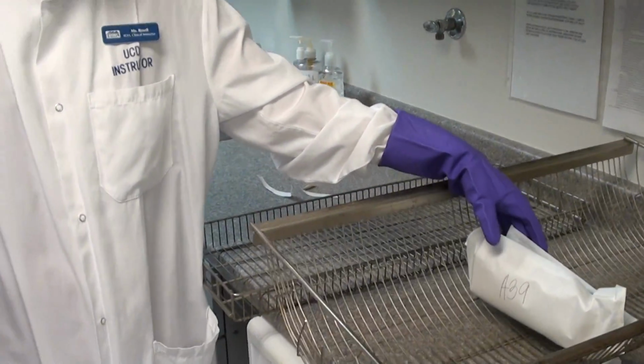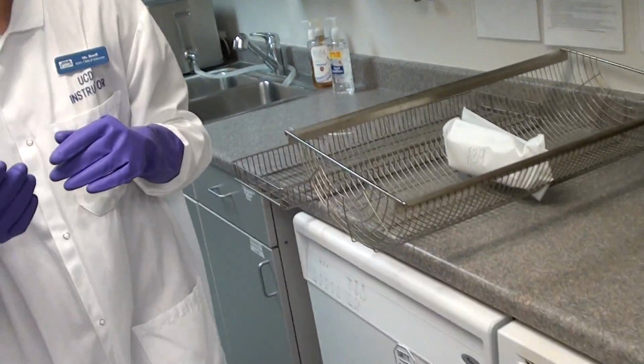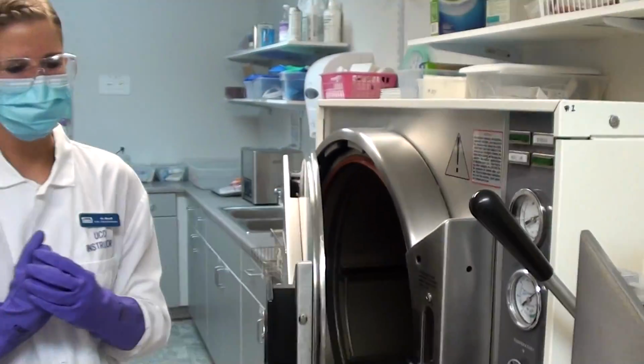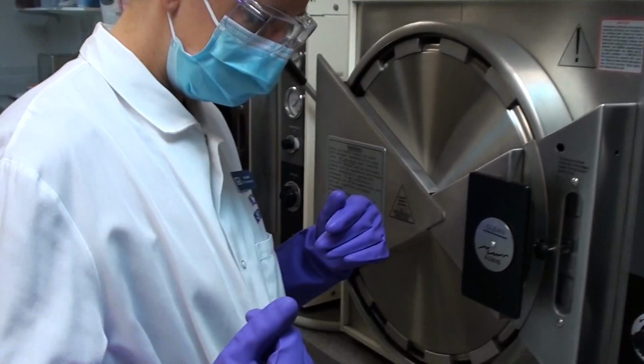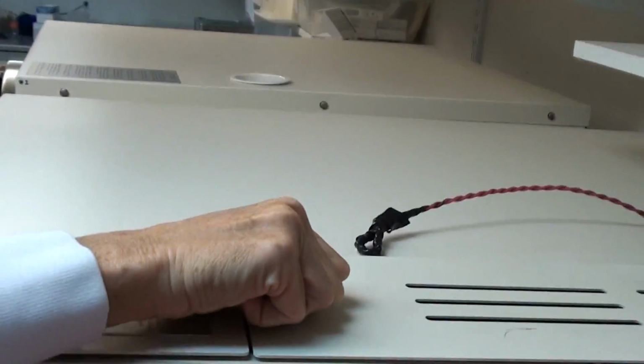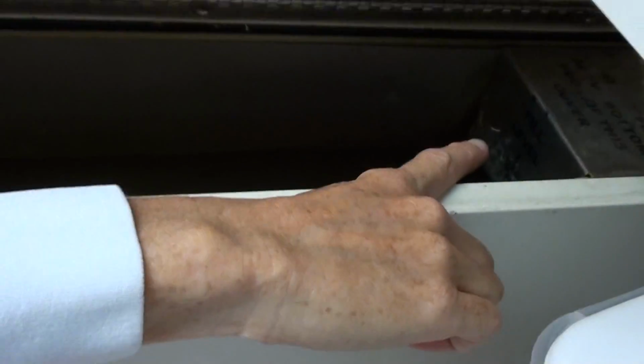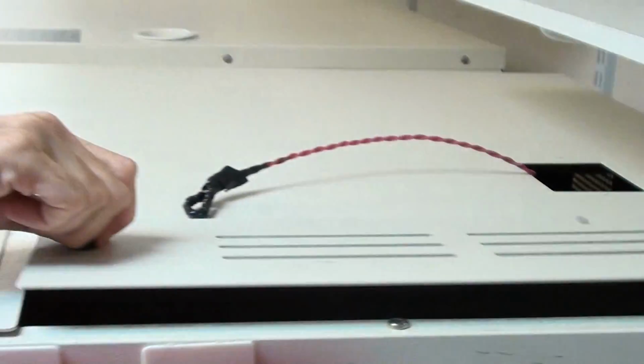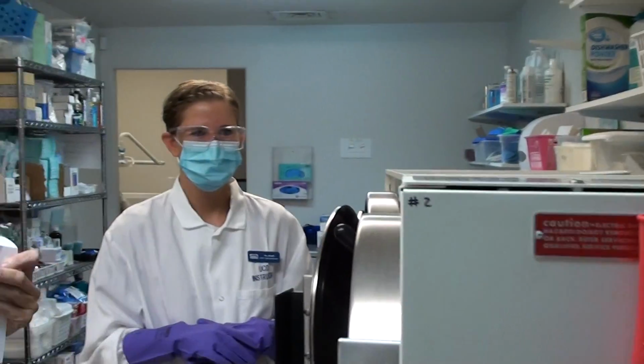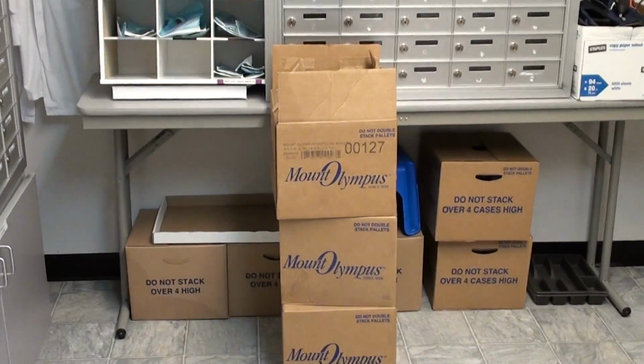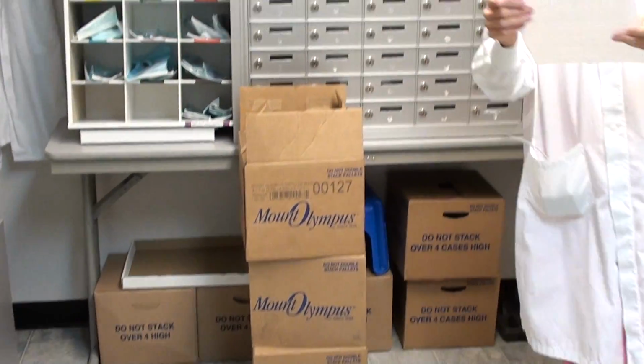Okay, now she's going to check the water level in the holding tank, and she's going to add distilled water if the level is more than 3 inches below the fill line of the holding tank. I'll have my friend look because I can't touch this with gloves. Kelly, I've gotten a stool for you. Can you check the fill level for me? I would love to. I'm going to stand up here and pull back this little door and look. There's a fill level, if you're confused, right over here. Looks fabulous. So I'm going to leave it, but if I needed water, we have our sterilization water over here. Do not use the water out of the sink, as the machines don't like that. It must be distilled water, so please use that.